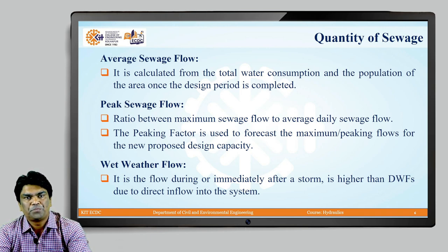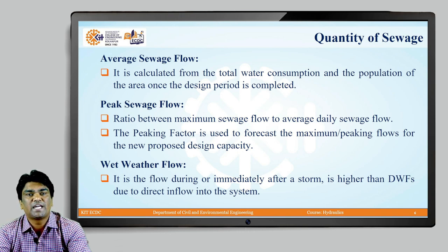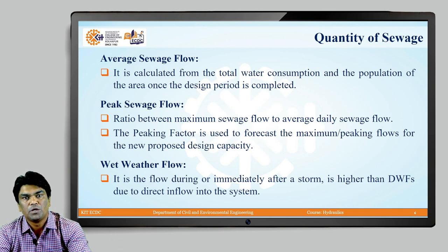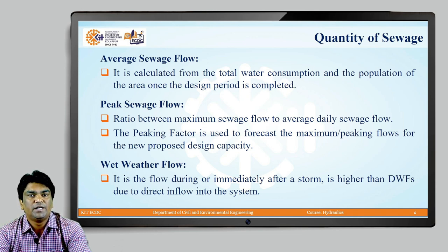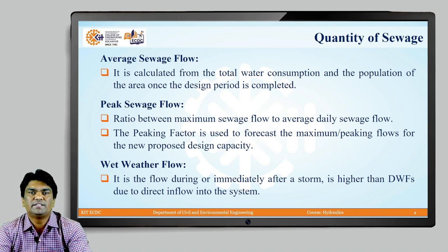The second flow term is peak sewage flow, which uses the peaking factor — a term used to forecast maximum or peaking flows for new proposed design capacity. It is the ratio of maximum sewage flow to average daily sewage flow. Wet weather flow is the flow during or immediately after a storm and is higher than dry weather flows due to direct inflow into the systems.